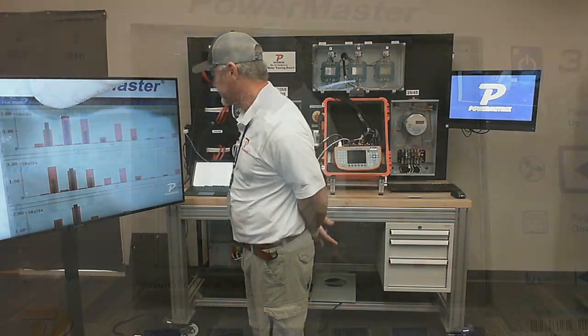Back in Knoxville, but you can see right here the choppiness on those waves - normally when you see choppiness like that, it's indicative of Harmonics. So we know there's some Harmonics going on here, and you can hear what's going on behind us. We talk about that in the class, but I wanted you to see it out in the field. This would be a site we'd know to keep in mind as a potential cause of a problem.